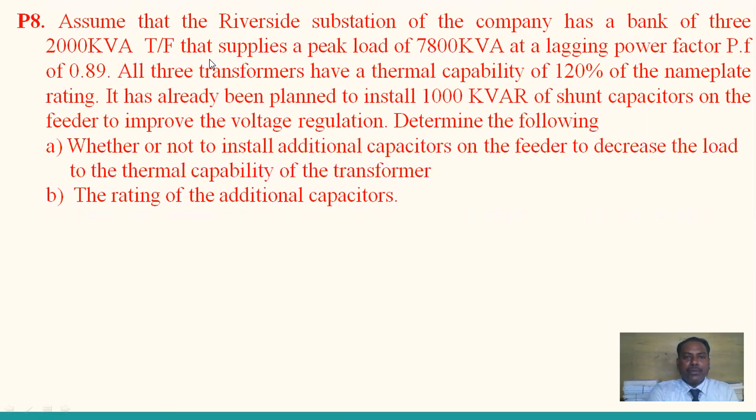Assume that the riverside substation of the company has a bank of 3 transformers, each rated 2000 kVA, that supplies a peak load of 7800 kVA at a lagging power factor of 0.89. All the 3 transformers have a thermal capability of 120% of the nameplate rating. It has already been planned to install 1000 kVAR of shunt capacitors on the feeder to improve the voltage regulation.